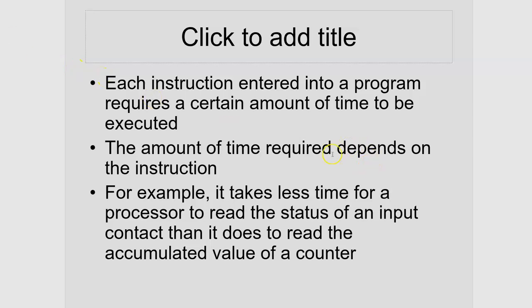For example, it takes less time for a processor to read the status of an input contact than it does to read the accumulated value of a counter or the value of a timer. You would expect that. I mentioned before that timers and counters are more complicated virtual devices. It takes more memory and more words of memory to reflect the counter or timer in memory, so you would expect it would take longer to read. So this idea of time is going to turn out to be important.